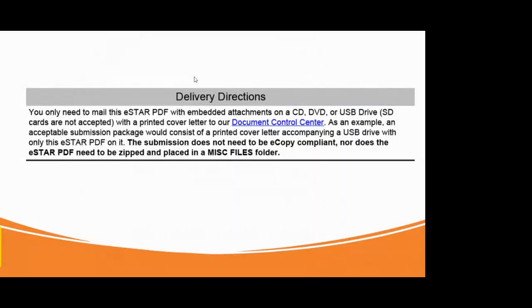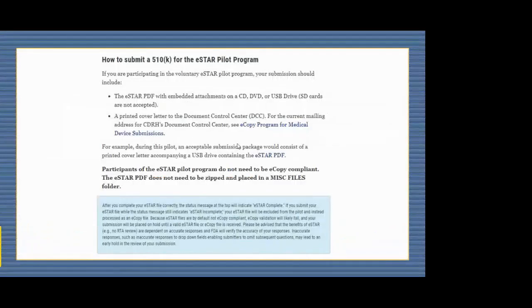On software. And again, note, and I want to emphasize at this time, one of the FDA slides, the 2 slides that I showed you earlier, actually makes a note of it, but I'm going to stress at this point, eSTAR is not available for e-submission. In other words, you cannot submit this to the electronic submission gateway, ESG, of the US FDA for the time being. After completing the eSTAR PDF with all the attachments, one has to do snail mail on this one. You have to package it up in either a CD, DVD, USB drive, print a cover letter, send it to the appropriate address, but there are plans to incorporate this within the electronic submission gateway of the FDA.